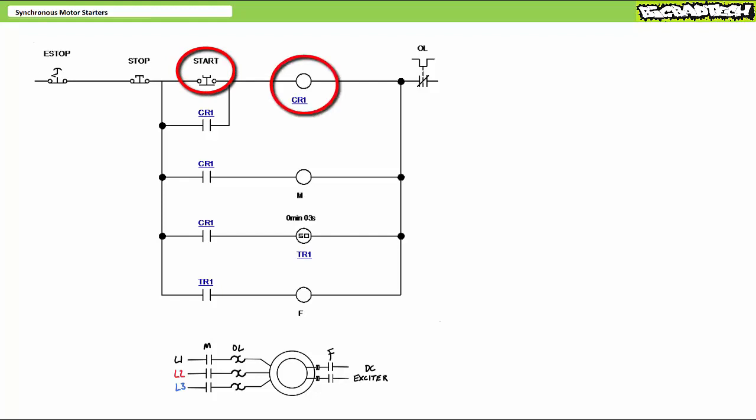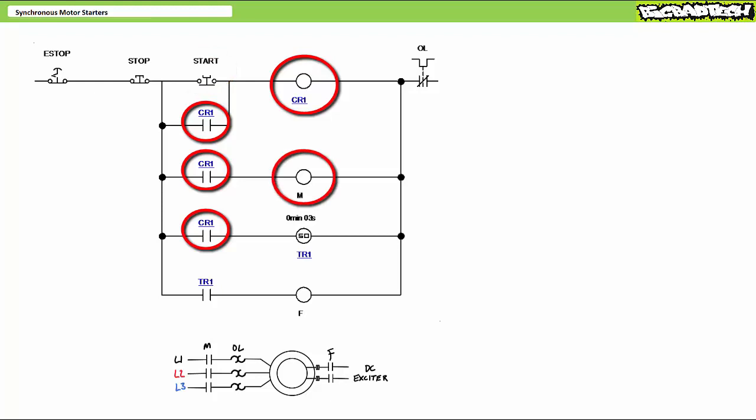When CR1 energizes, its associated contacts in rungs 2, 3, and 4 simultaneously change states. CR1 in rung 2 closes and establishes a holding circuit allowing the operator to release start. CR1 in rung 3 closes and energizes the M primary contactor coil. The M contactor closes and the motor starts.